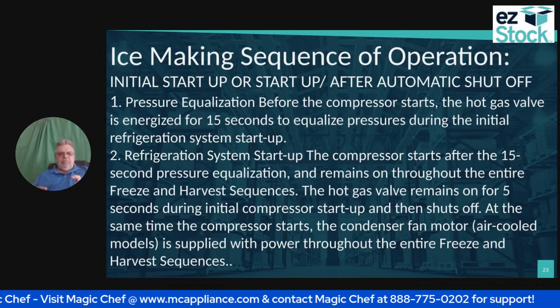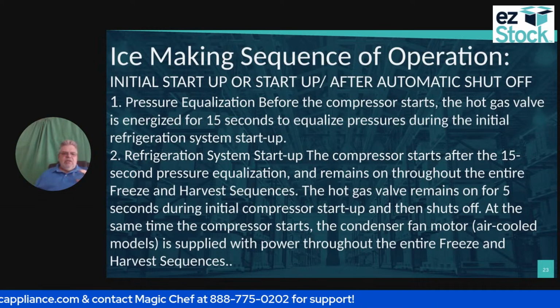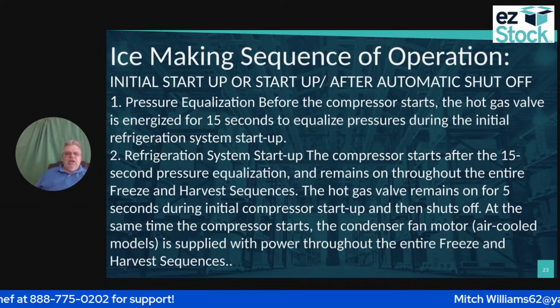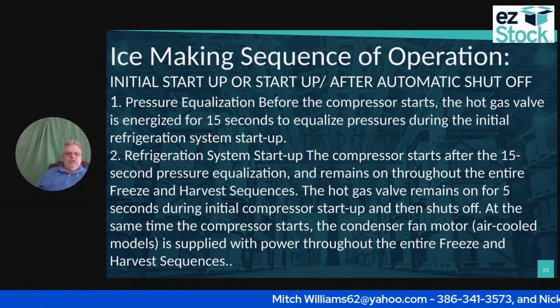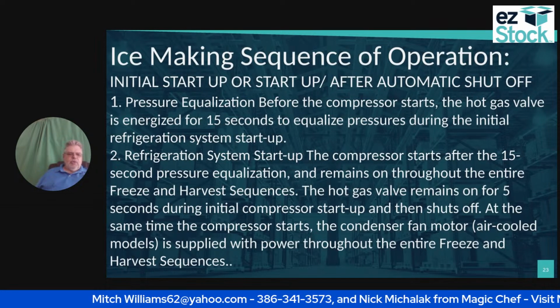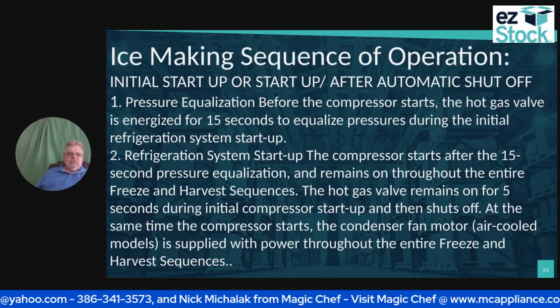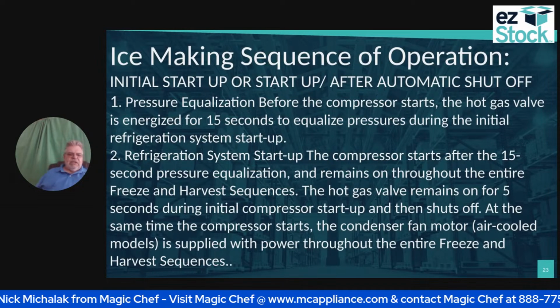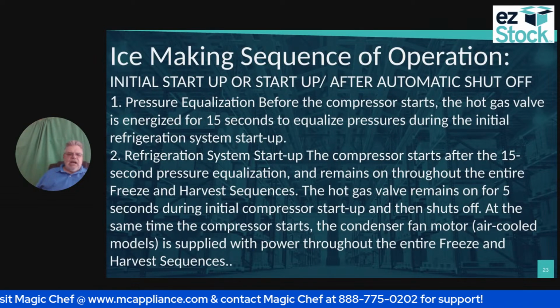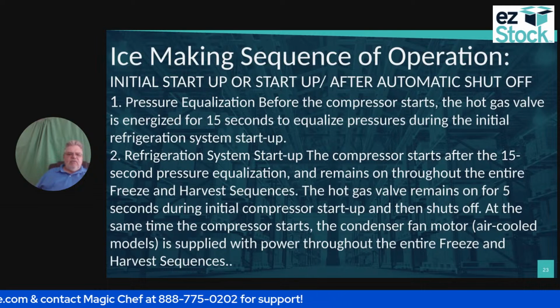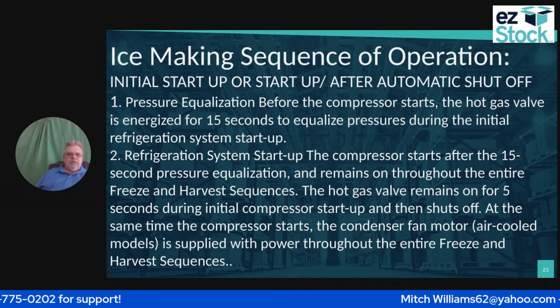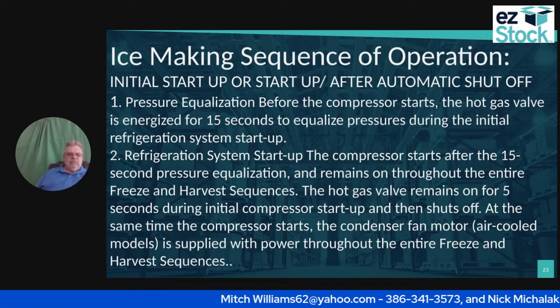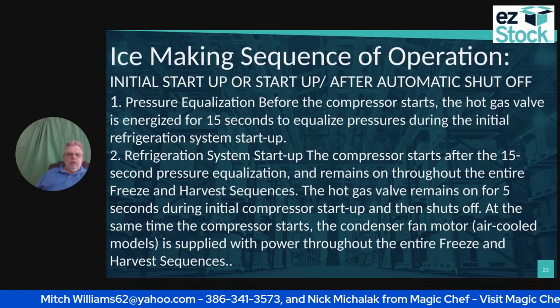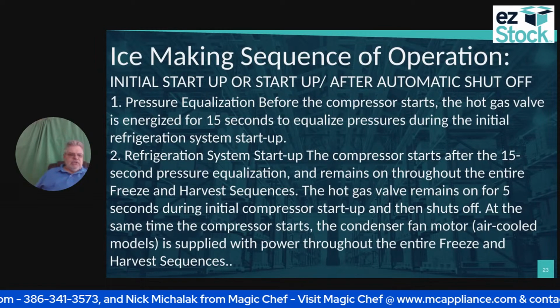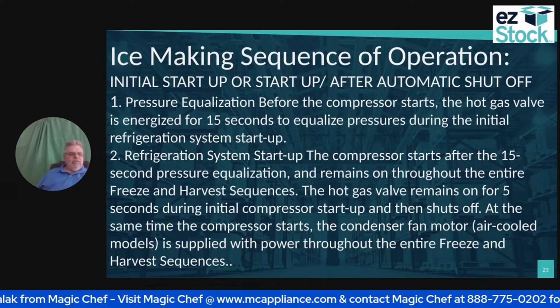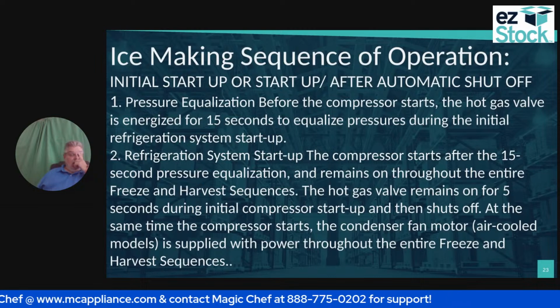From the initial startup, the first thing that happens is the pressure equalization before the compressor starts. The hot gas valve is energized for 15 seconds to equalize the pressures during the initial refrigeration system startup. Okay, the compressor starts after the 15-second pressure equalization and remains on through the entire freeze and harvest cycles. The hot gas valve remains on for 5 seconds during the initial compressor start and then shuts off. At the same time the compressor starts, the condenser fan motor on any air-cooled model starts, and it runs all the way through the entire freeze and harvest sequences.